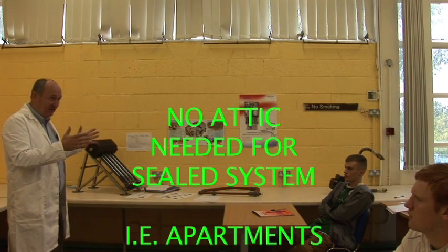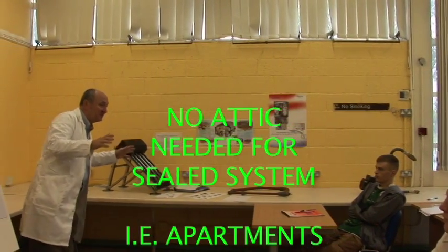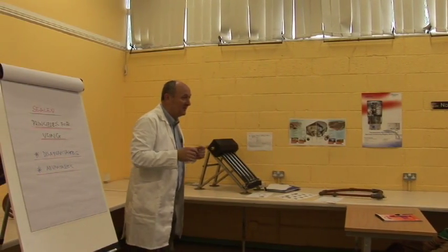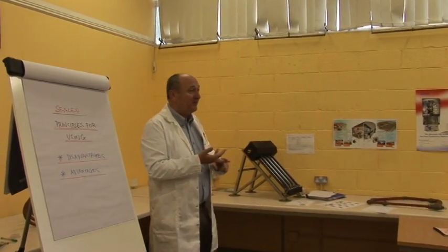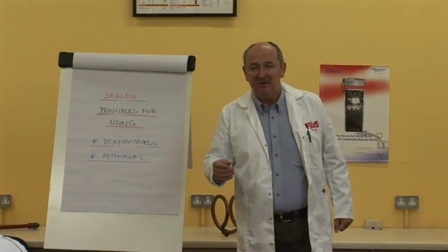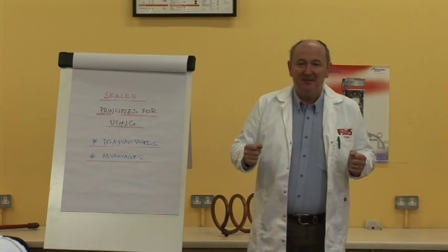The sealed system also has the advantage that you don't have to run pipework into your attic at all. You can install an oil or gas system without getting into the attic or loft. You're eliminating pipework in the attic, eliminating the risk of frozen pipes, and eliminating the need for heavy insulation up there. There's a cost saving on the sealed system when you take into account all the things you don't have to do compared to the open vented system.